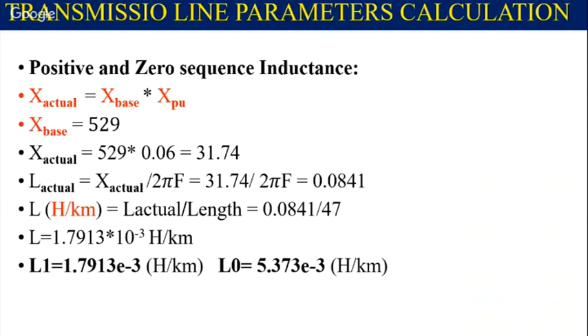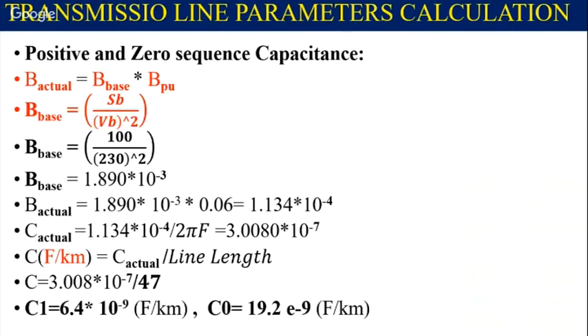Once you know the resistance value calculation, it is the same for inductance. Similarly, for susceptance, instead of base impedance, we have to calculate base admittance. The formula will be reversed, that is MVA upon kV square, which will give the base value of susceptance. From there, you can calculate the actual capacitance. From the capacitance value, you can get farads per kilometer, that is divided by the length of the line.